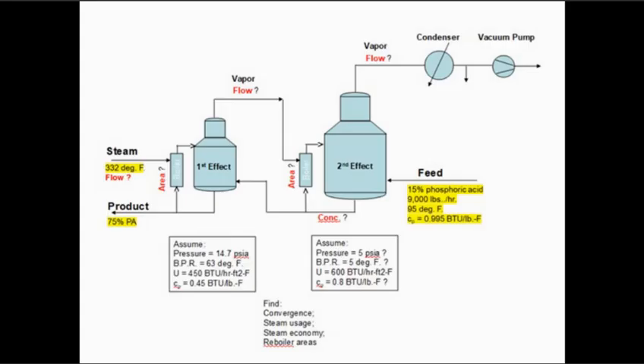So let's look at this example. This diagram depicts a double-effect evaporator. The flow path of the liquid feed and the product is from right to left, as opposed to what one may typically expect. The reason for this is such that we can think more in terms of vapor flow, which is the flow from left to right, as it is the one that is serving the more unusual purpose in this process, and as the evaporator effects are conventionally numbered.